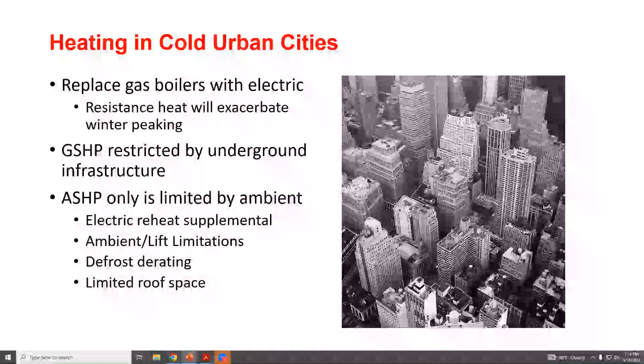So what that means is there are certain points where air source heating products do not operate in a given ambient temperature. And then lift is a concept of, at a given ambient temperature, how high up you can raise a temperature from your source of heating - so how high of hot water can you produce. There's certainly limits within the air source products. Defrost derating, we heard about this a little bit - when there's moisture in the air because we're pulling heat out, we may form ice on a coil, and we have to consider defrost within our sizing of systems, as well as limited roof space.